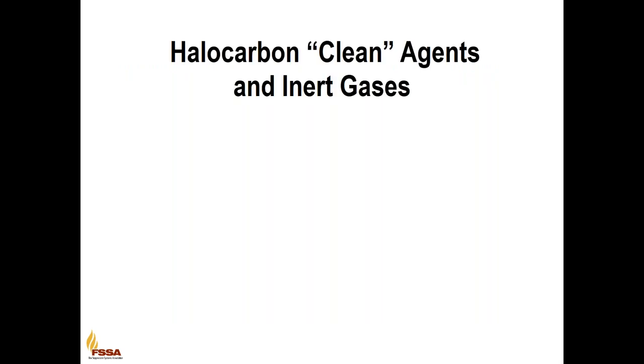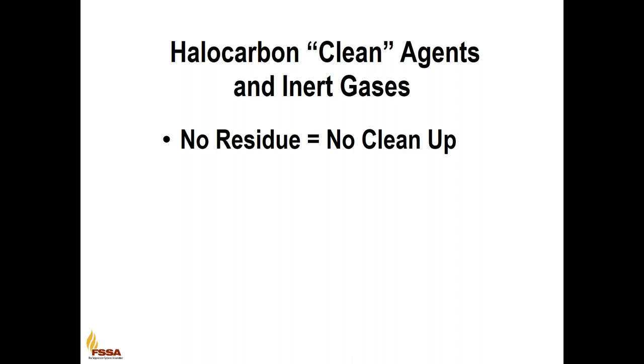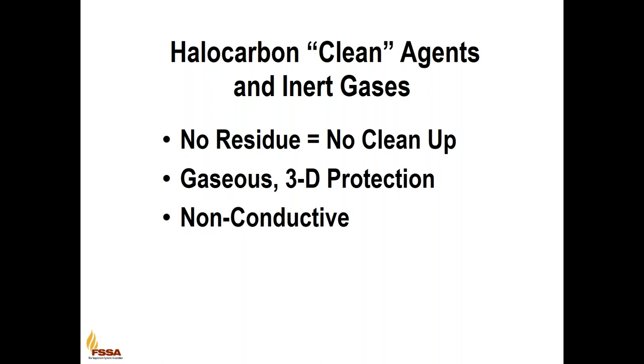If we look at the specifics of each agent, it's important to know that there are several factors common to each one in this group. They're all considered clean agents, meaning there's no residue and no cleanup after a discharge. They are gases with the ability to suppress a fire from a 3D perspective. Also, they are non-conductive, which means they're safe for use to protect energized electrical equipment. And more important, they may be used at concentrations which are safe for people and used in occupied spaces.